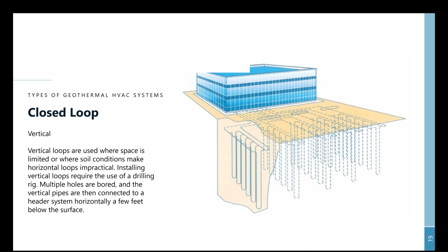So what does a vertical geothermal borehole look like? Here you can see the image on the far right shows what we call the U-tube heat exchanger, or the U-bend heat exchanger, typically made out of high-density polyethylene pipe, or HDPE pipe. That pipe is going to be a closed loop filled with either water or a water and antifreeze mixture. The antifreeze comes more into play when you're in colder climates that are going to experience lower ground loop temperatures, and you have to add an additive to the water to make sure that it does not freeze.